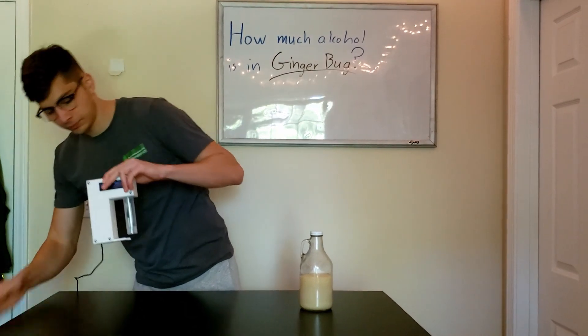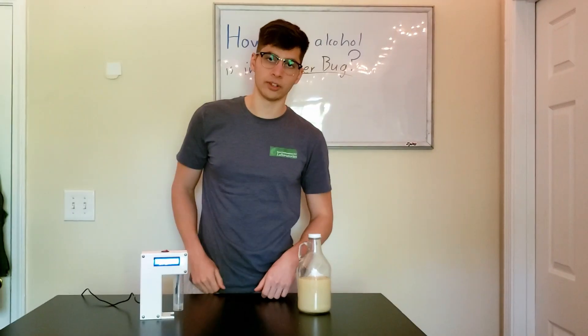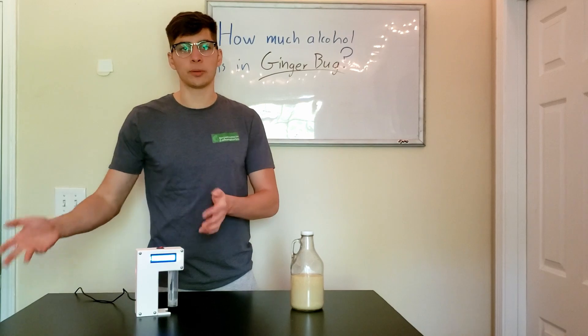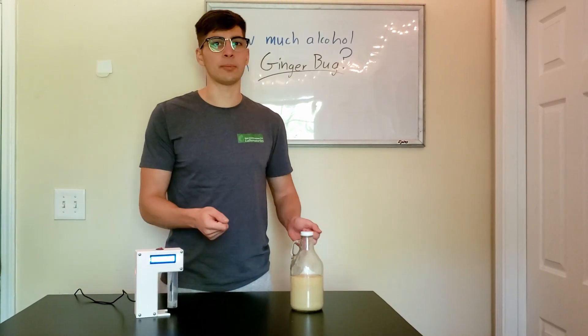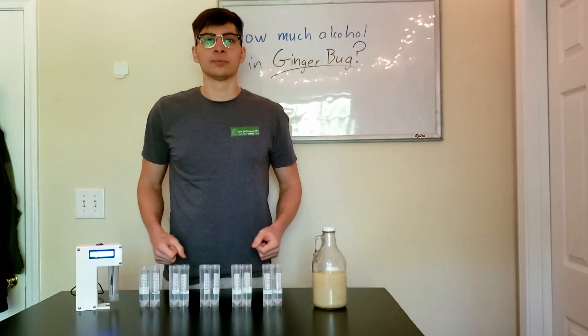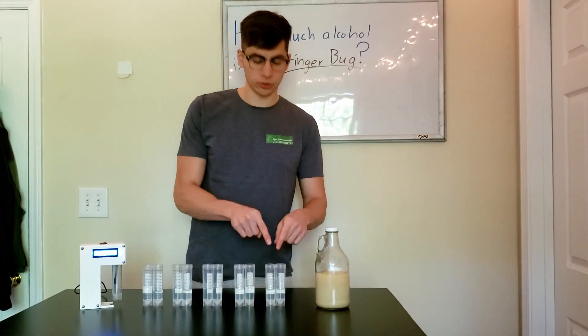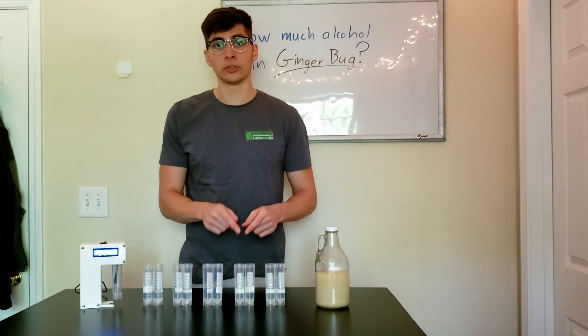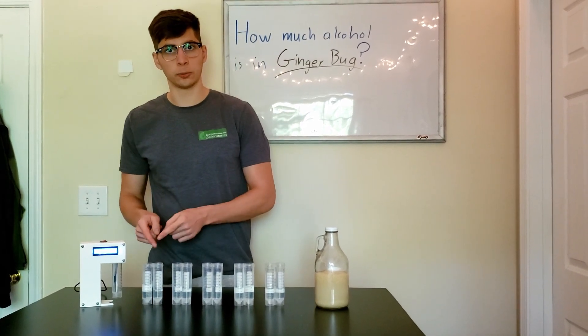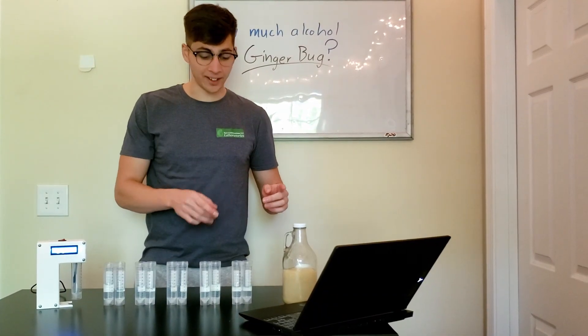I'm going to plug it in and turn it on. So now I can go ahead and get my calibration samples ready and get my laptop out to set up the calibration curve. We have all of our calibration samples poured: our 0.1% standard, 0.25, 0.5, 1% and 2%. I got my laptop now.